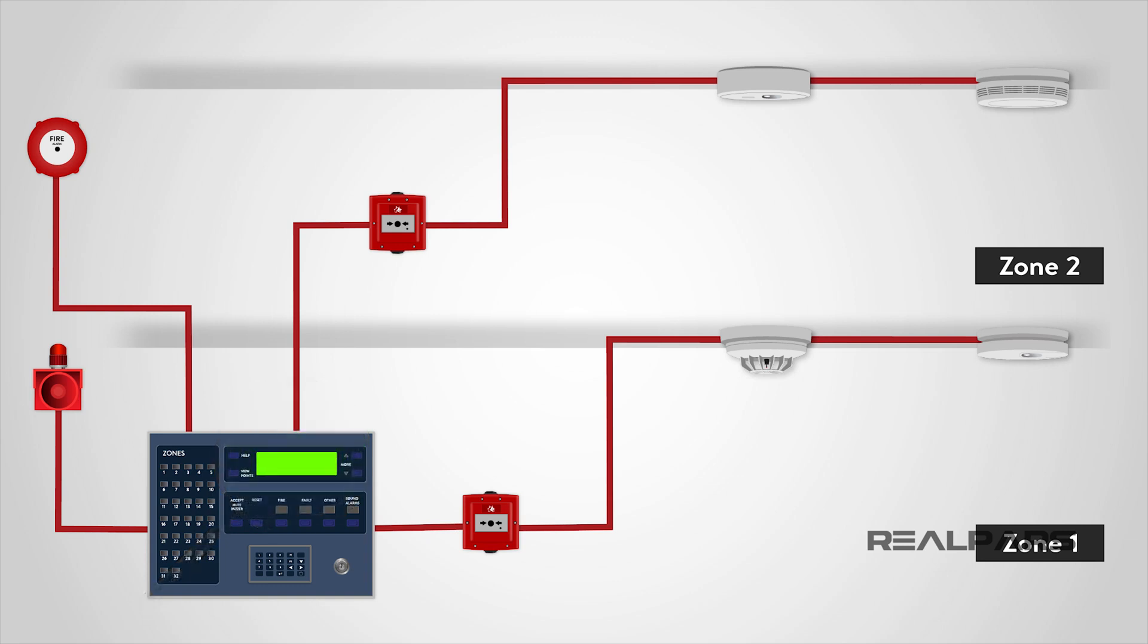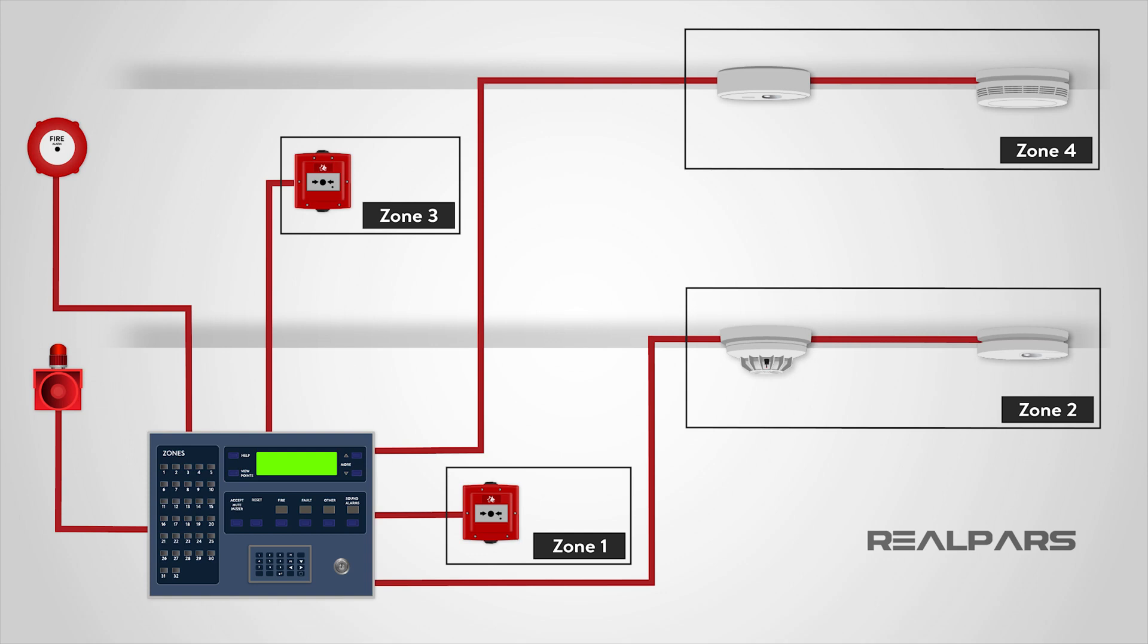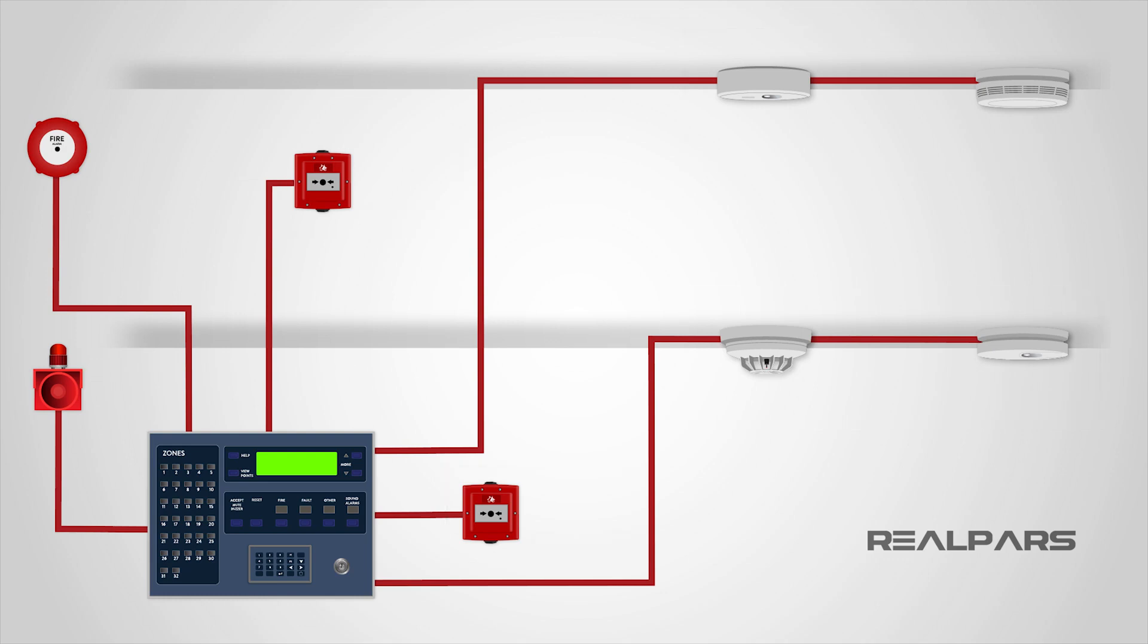It makes sense that the more we can divide a building into zones, the more accurate locating the alarm trigger will be. The control panel is wired to a minimum of two sounder circuits which could contain bells, electronic sounders, or other audible devices. It is these devices which sound the alarm when triggered.